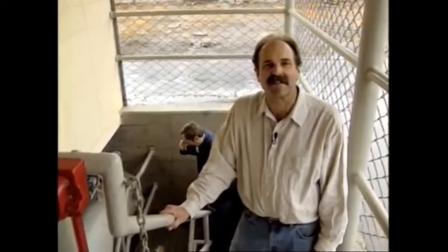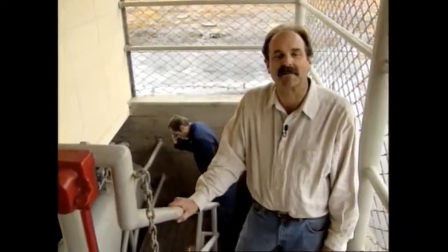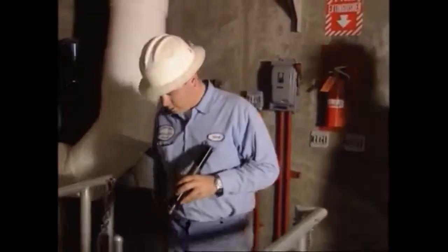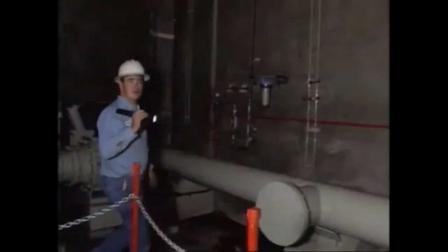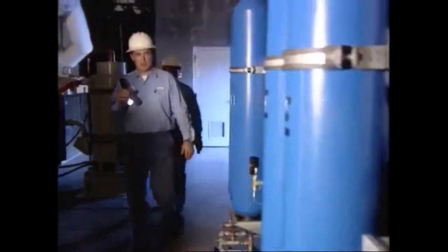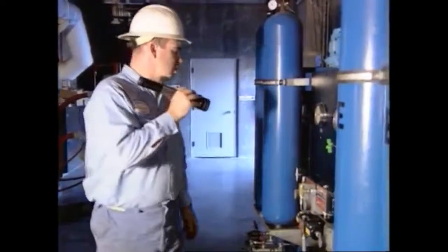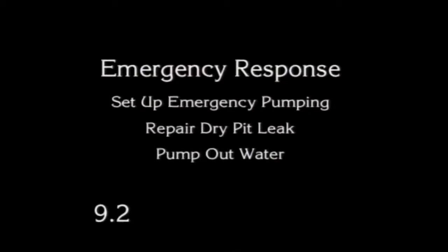Next, turn your attention to the station wet pit area. Examine this area carefully to make sure that it is not flooded. Another area to check is the dry well area. If it's flooded, don't restore power to operating equipment if power is out. If electric motors are flooded and won't start, open main power switches to avoid providing electricity to the area. If you're not qualified to operate or perform checks on electrical systems, don't do it. Request help in setting up emergency pumping equipment. Locate and repair the leak to the dry pit. Pump the water out of the dry pit with portable pumps.